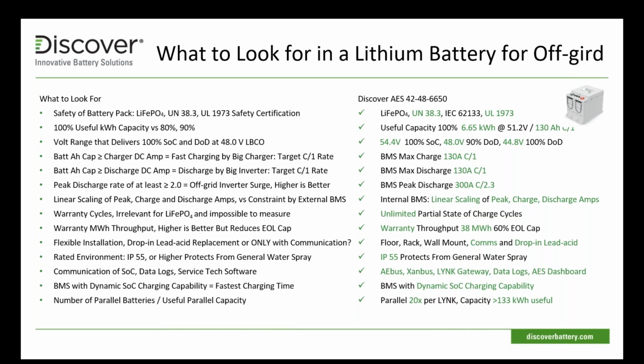So our battery delivers 100% state of charge at 54.4, which is quite a reasonable voltage. You'll see other batteries with much higher voltages there, which will actually stress the cells in the pack and lead perhaps to premature demise. Our battery at 48 volts is 90% depth of discharge. And 48 volts is significant because that's the low battery cutout of a majority of inverter products out there. So have a look at that number and where that happens. We can go as low as 44.8, which is our 100% DOD there. So it's important to note where the product tops out.